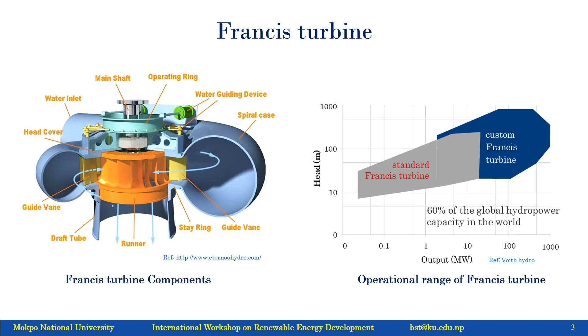If you look towards the design philosophy of the Francis turbine, in order to have a very high efficiency, Francis turbine claims to have more than 96% of hydraulic efficiency. To obtain this efficiency, the water in the spiral casing, which is moving around 10 to 15 meters per second, accelerates quite rapidly, and before it exits the guide vane, 50% of the total head is converted into the velocity head. So that brings the very peak velocity at the guide vane periphery.